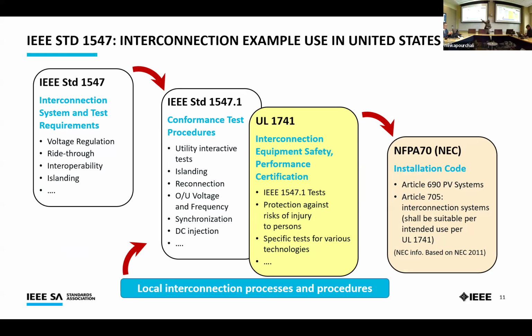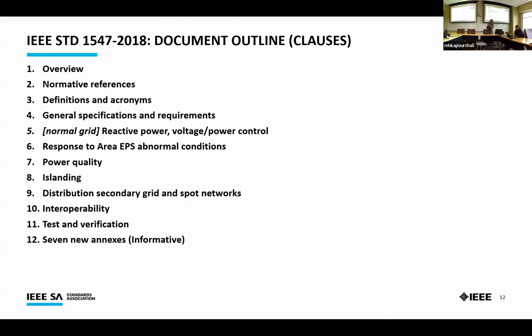UL 1741 standard is an important thing - that's how you certify that device. So if an inverter is listed UL 1741, it's been certified by UL and tested by an NRTL that it's compliant. That's an important point in terms of standards development - once it's published, it's a great way to have conformance and compliance. One way is to have UL certification. So UL 1741 is a certification to verify that a listed device is compliant with IEEE 1547.